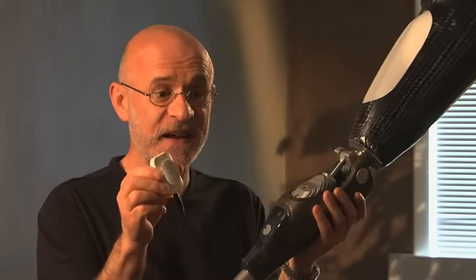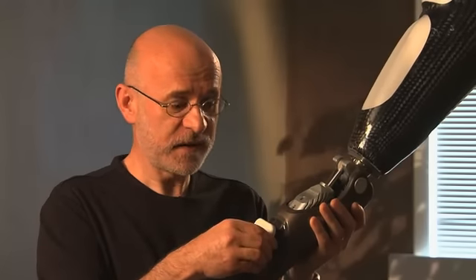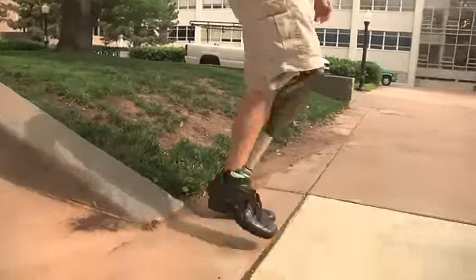This is a very simple charger — it has a little magnet attached to it that clicks right onto the limb. Very, very simple. Many of our prosthetic users have asked us for extended battery life in their knee, and this one delivers. It lasts four or five days. But in fact, let's say you're on a camping trip and you don't have any access to electricity at all — you can extend the battery life for up to eight or nine days by actually turning it off at night while you sleep.